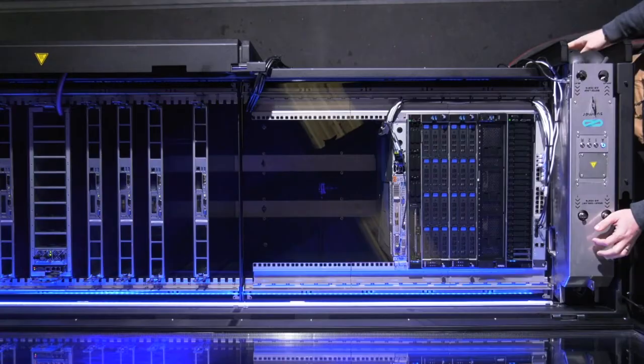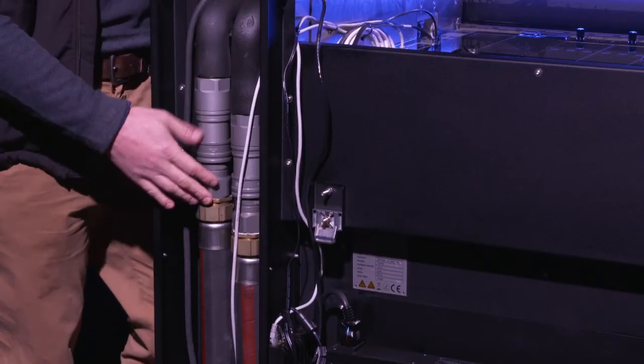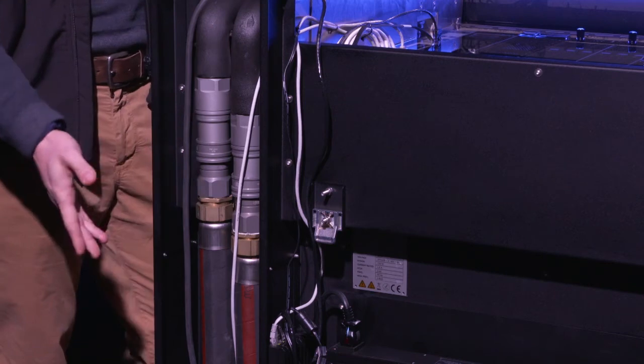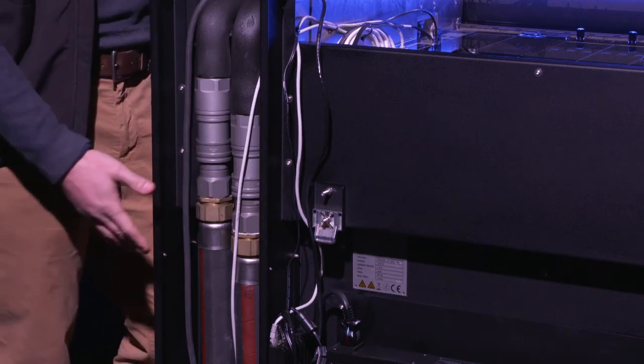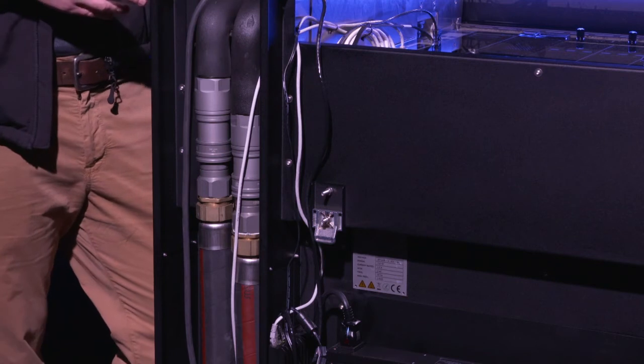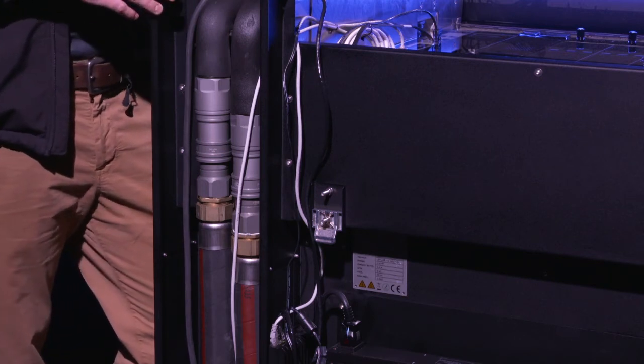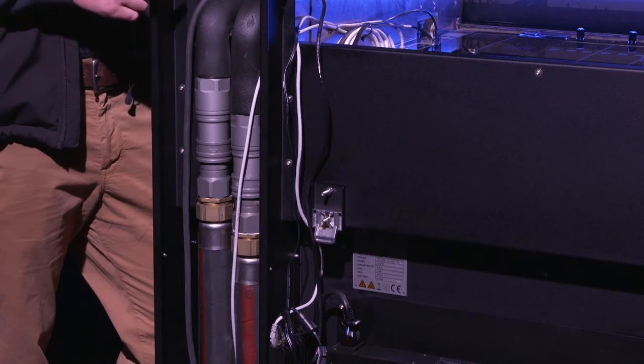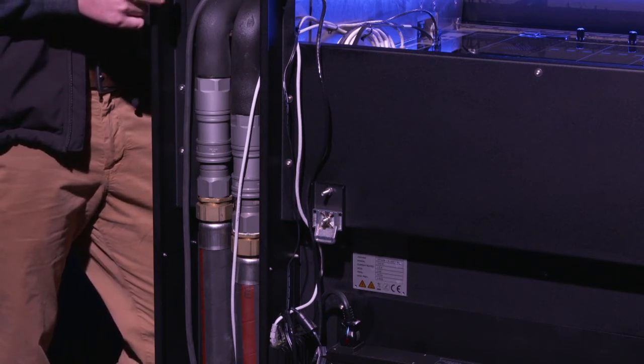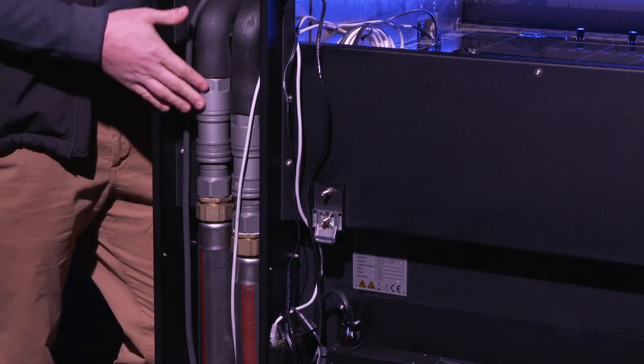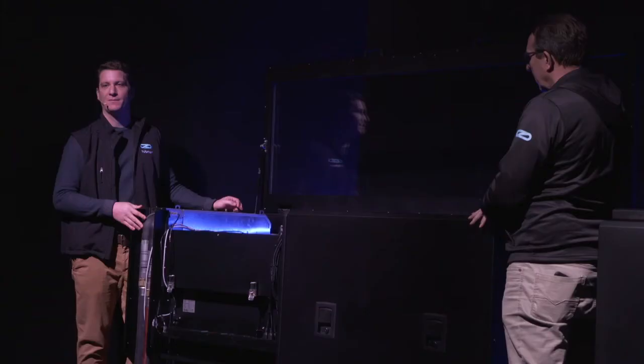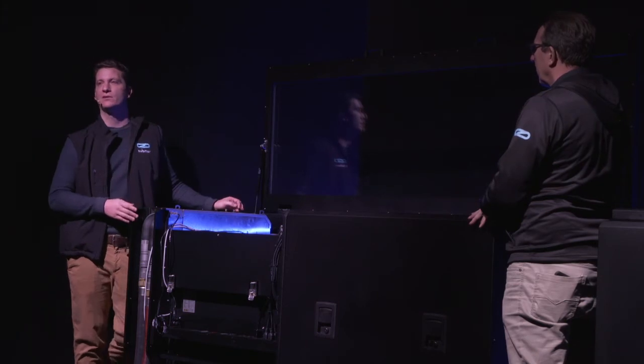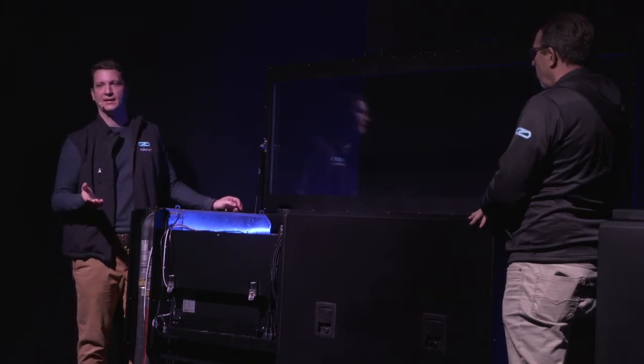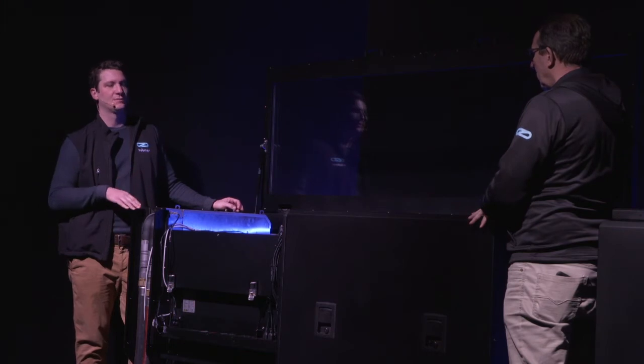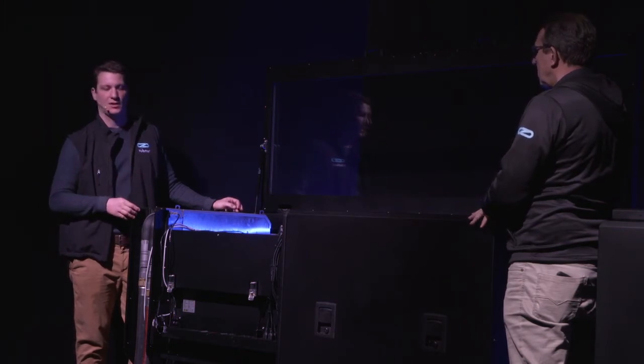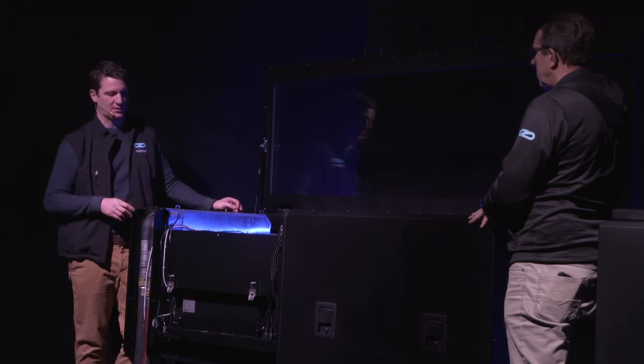disconnecting the quick disconnects. So these hoses will connect with the facility water. They're flexible hoses that typically would connect to the major distributor pipes that are supplying the water feed to the immersion tanks or other types of systems in the data center that require water. And again, this water loop runs at very high temperatures, typically in the range of 40, 45 degrees centigrade, which means, again, we can work with these systems anywhere on the globe with dry cooling technology. Again, connecting with that zero water consumption.